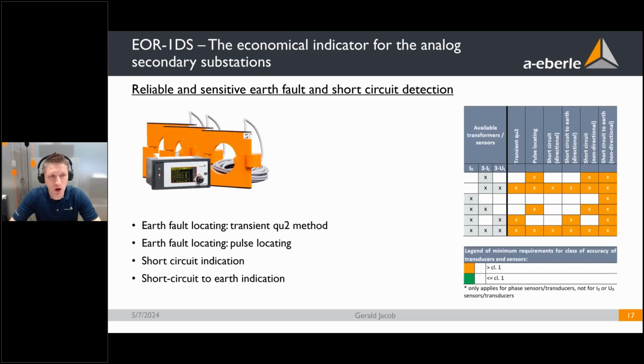Here a small overview that you can also find in our datasheet about the possible algorithms for earth fault detection and short circuit indication, depending on the measurements that you have. For example, in the first row, you can see when you only have 3 times the measurement of the current, you have as possibilities the pulse location in compensated networks and the undirected short circuit and short circuit to earth indication.